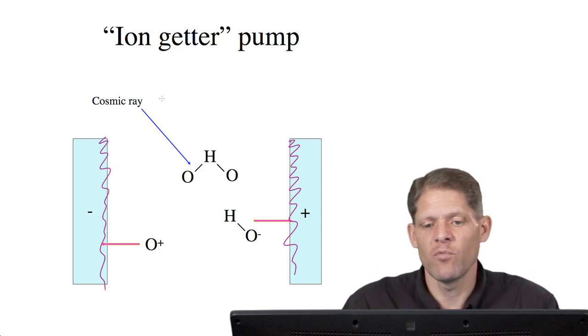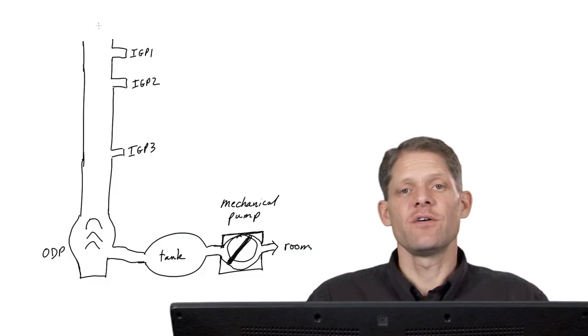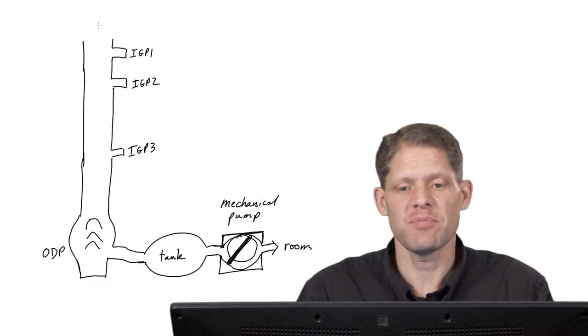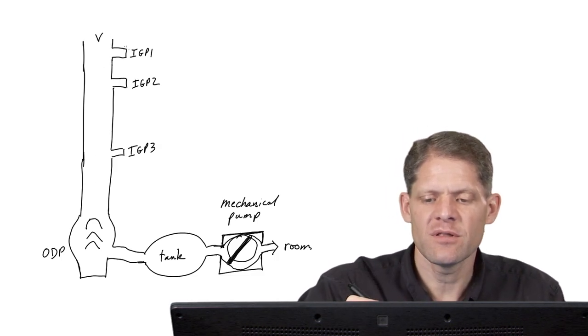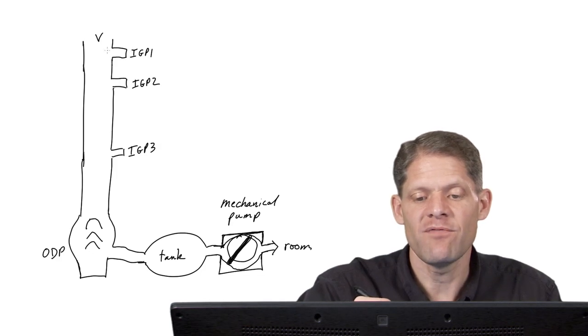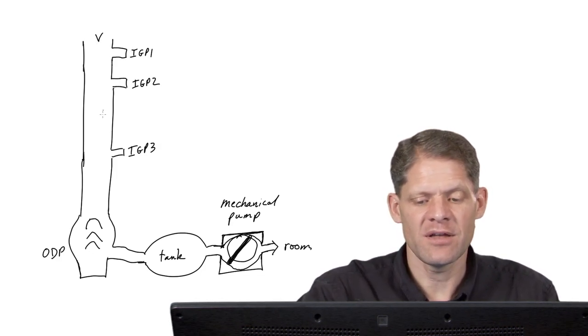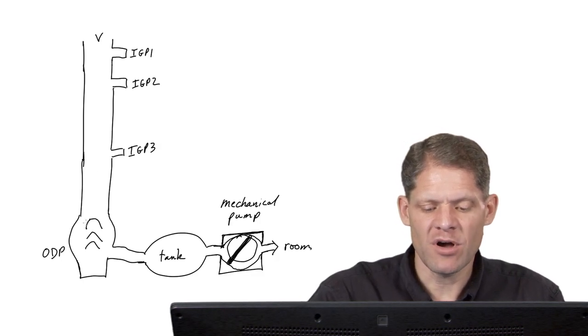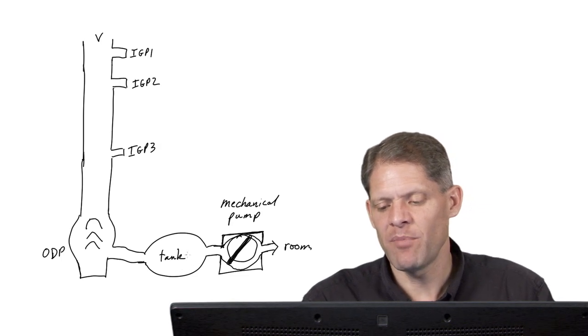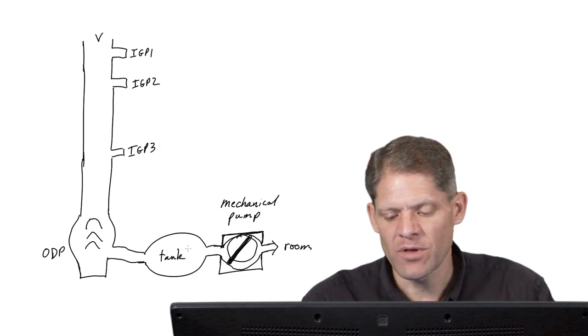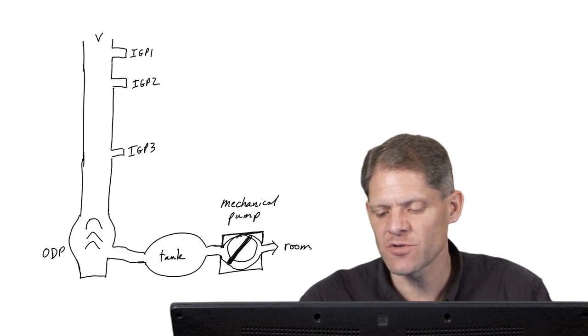The full vacuum system, therefore, is pretty complicated. For instance, in the column, by the filament, there is probably an ion-getter pump evacuating the area just around the gun. There are other ion-getter pumps within the column. At the bottom of the column, there is the oil diffusion pump, and that is backed by the mechanical pump with a storage tank, a buffer tank in between, and the mechanical pump exhaust to the room.